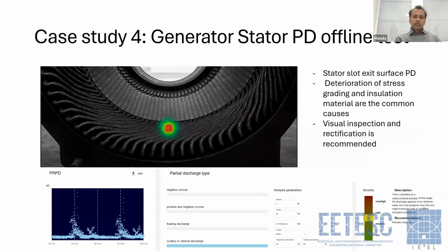Okay, let's go to case study number 4. In this case, generator stator PD offline. So the generator is not in working condition. The rotor is being extracted and the generator stator is being tested with an offline partial discharge test, usually with high voltage AC. In that case also we can use acoustic cameras to detect partial discharges, for example, on the stator bars.